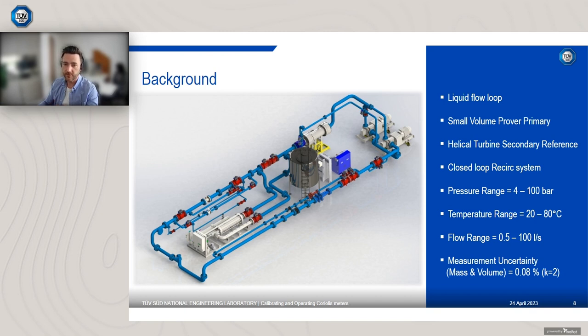We have a pressurization unit there, so we can quickly change pressure. Because oil is fairly incompressible, has a low compressibility, simply adding an additional amount of oil via this pressurization system, which is controlled via a feedback loop, we can increase the pressure from between 4 to 100 bar. Now, if we were operating at say 10 bar and we wanted to go up to 100 bar, it only takes around 10 to 15 minutes to go all the way up to 100 bar and achieve stability.